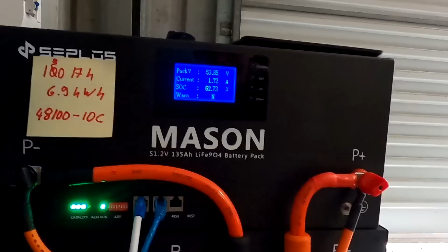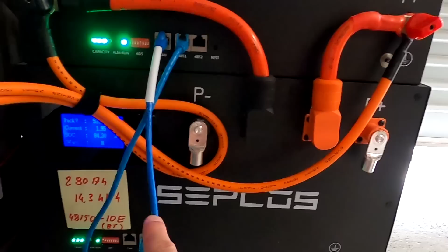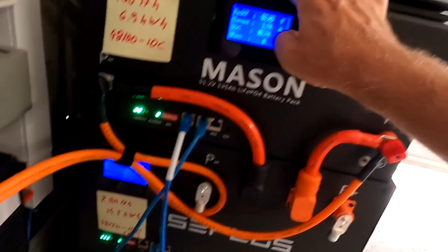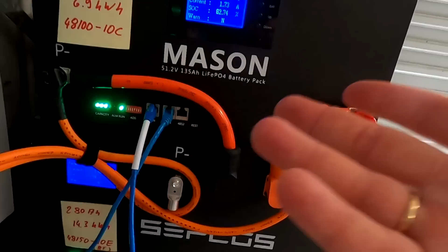Wait, before you go. I've just reconfigured the batteries again, so made the top one the master and left the bottom one as the slave. And look what is reporting now. The Victron system shows now 270 ampere hours. So the master battery here, the top one with 135 ampere hours, times 2, because we've got two batteries connected, 270 ampere hours, right? This is exactly what it reports to the Victron system, but we are still having 411 ampere hours available.